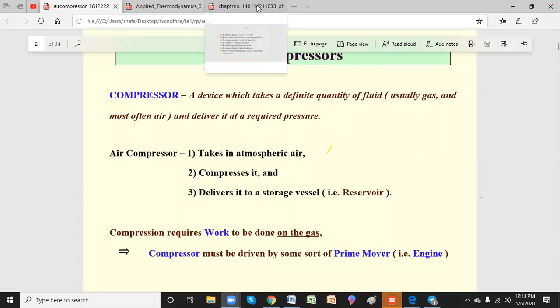Now, this second point here shows what operations the air compressor will perform. First, it takes atmospheric air, then it compresses it and delivers it to the storage vessel. Normally, the storage vessel is called a reservoir. Compression requires work to be done on the gas. If you take an engine, that delivers work or power for us, but a compressor requires a prime mover, either a motor or an engine. So the compressor doesn't run on its own, it has to start, then only it will take the fluid from the atmosphere, then start compressing it to the higher pressure. That's the basic function of your air compressor.